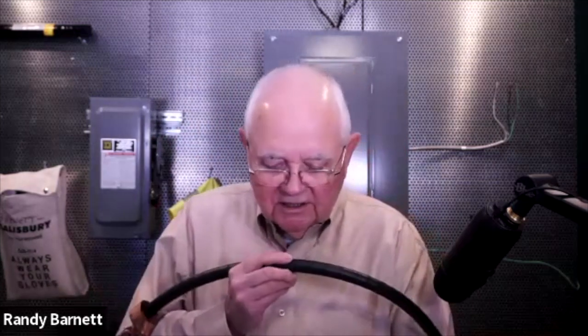315.10(A) says conductor applications and insulation rated 2001 volts and higher. It says the trade name is medium voltage solid dielectric cable, which, yes, this is solid insulation. And it says the type letter is either MV90 or MV105. Well, this says on here MV90. Okay, so MV90. Taking a look at Table 315.10(A), it says that MV90 means that the maximum operating temperature is 90 degrees C on this particular conductor, and suitable for dry or wet locations.